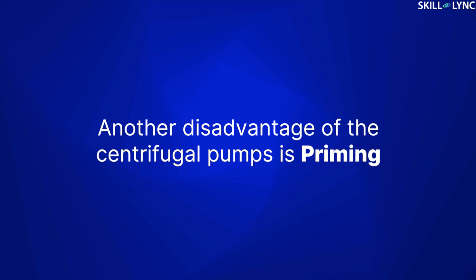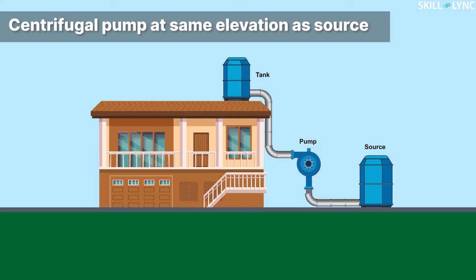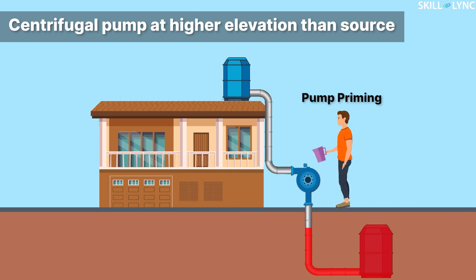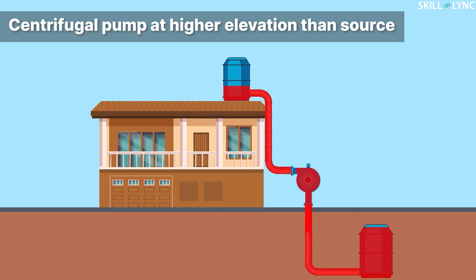Another disadvantage of centrifugal pumps is priming. Priming is required when the elevation of the pump is more than the elevation of the liquid. The impeller is not able to generate sufficient suction pressure to lift the water against gravity from its resting surface. This is because a centrifugal pump works by pushing the water through centrifugal force instead of sucking it. Because of this, the impeller needs to be primed, which is normally done by filling the casing and the pipes of the pump with the working liquid. An external priming port is provided to do this.